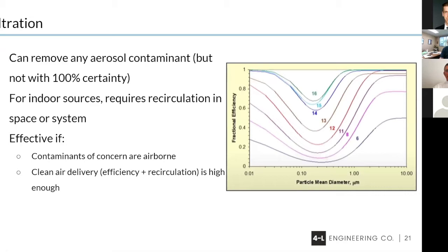If we look at the efficiency effect of a filter right here, and if you'll look at the MERV 6 there with your pointer, Bob, move down to the bottom right there. Right there at the bottom, you'll see that a MERV 6 will collect particles in the neighborhood of around 0.25, but if you move the chart to the left-hand side, it only has an effective use of around 10%.